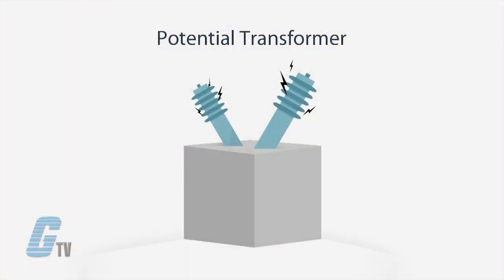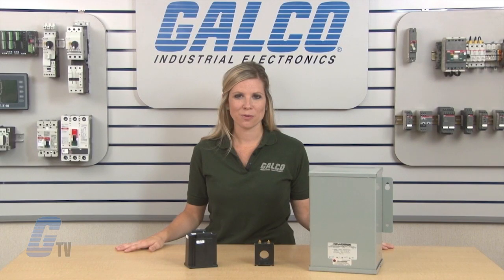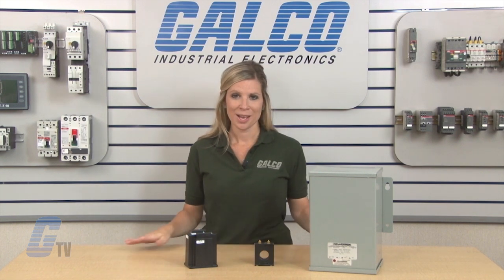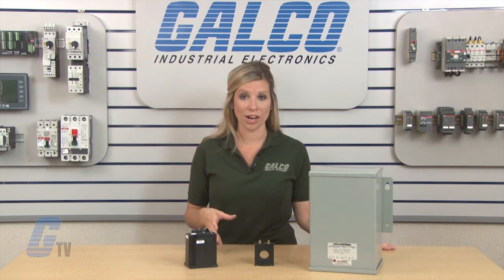A potential transformer is an extremely accurate step-down transformer, normally used with a standard 120 volt voltmeter. By multiplying the reading on the voltmeter by the ratio of transformation, the user can determine the voltage on the high side. In general, potential transformers are similar to a standard two-winding transformer except that it handles a very small amount of power. Transformers for this service are always the shell type because this construction has been proven to provide better accuracy.